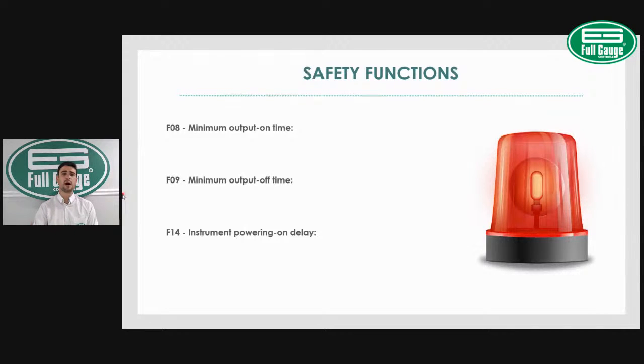And instrument powering on delay. What's the purpose of this feature? Again, when you have a power failure. So let's say we have 5 pieces of equipment in one site. We have a power failure. If each controller is set with a different power on delay, each piece of equipment will go on at a different time and will prevent that electricity peak. So F14 is good when you have multiple pieces of equipment in one site.